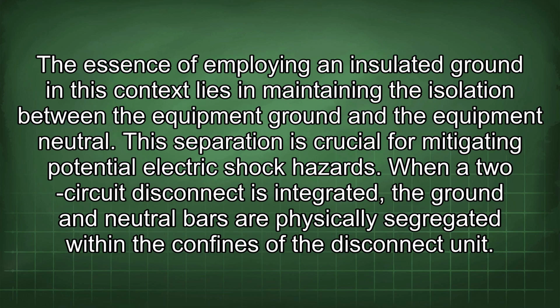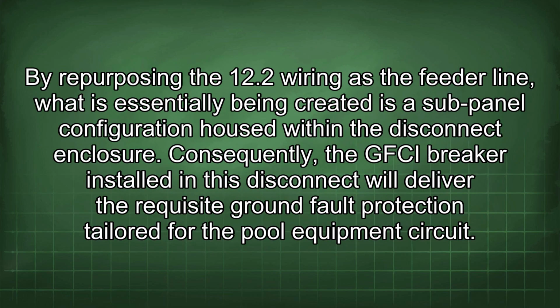The essence of employing an insulated ground in this context lies in maintaining the isolation between the equipment ground and the equipment neutral. This separation is crucial for mitigating potential electric shock hazards. When a two-circuit disconnect is integrated, the ground and neutral bars are physically segregated within the confines of the disconnect unit. By repurposing the 12/2 wiring as the feeder line, what is essentially being created is a sub-panel configuration housed within the disconnect enclosure. Consequently, the GFCI breaker installed in this disconnect will deliver the requisite ground fault protection tailored for the pool equipment circuit.